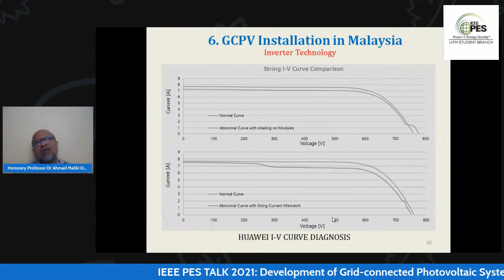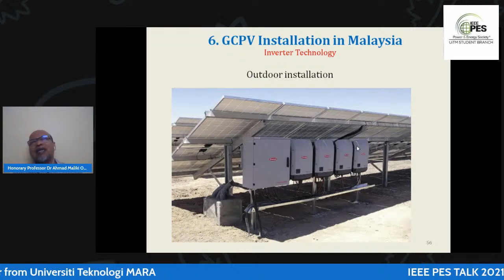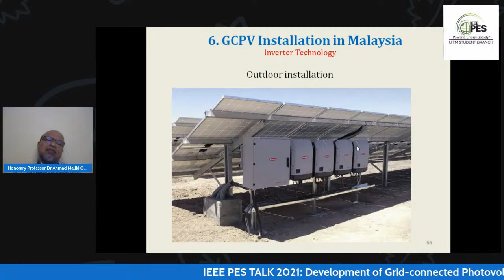This is the outdoor installation in Malaysia. Malaysia has hot climates throughout the year, except maybe in December during the monsoon season. But the inverter is very sensitive with temperature. So during installation, when we install the inverter, we have to ensure it's under the shade. Although the inverter is rated IP65 for outdoor installation, that doesn't guarantee the temperature will not affect the performance. So we normally install inverters under shade.